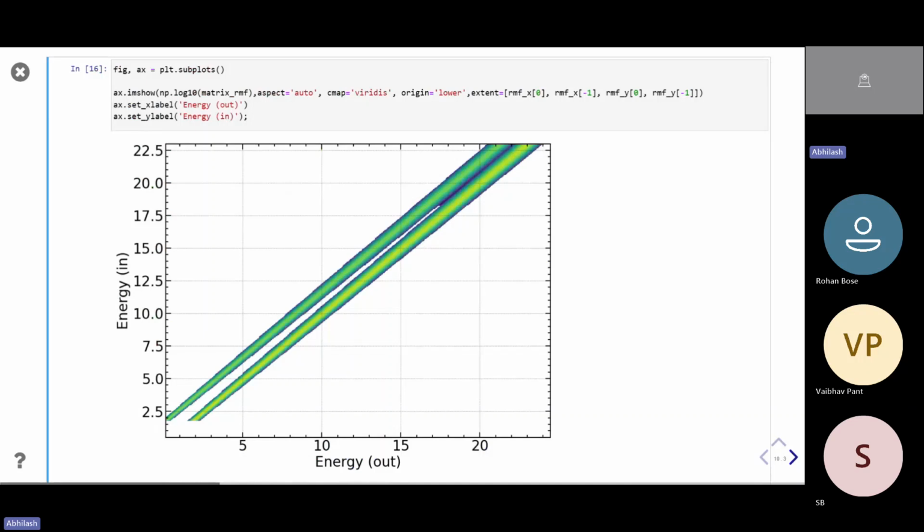So what happens if an X-ray photon is incident on the active volume, which is made of silicon? It can create a K alpha photon. The photon can knock out the K shell electron, and that vacancy can be filled by some M shell or L shell electron, and that photon can escape from the active volume and is not detected here. Say you have energy E, and a photon of 1.74 keV comes out that is not detected by the detector at all.